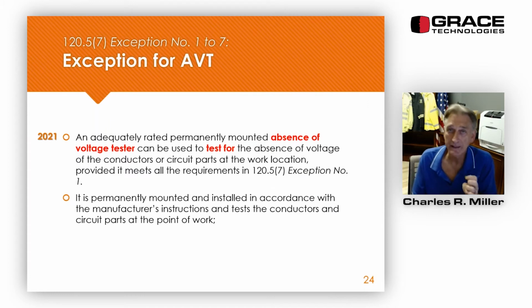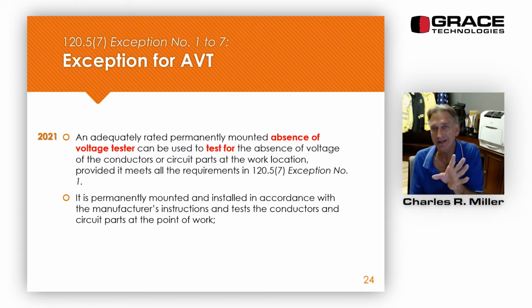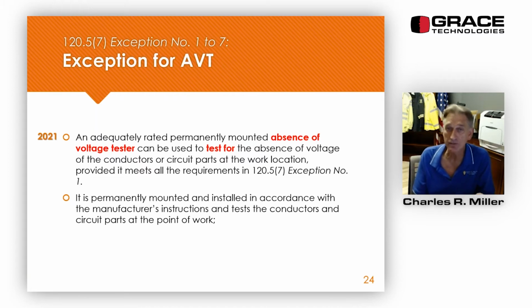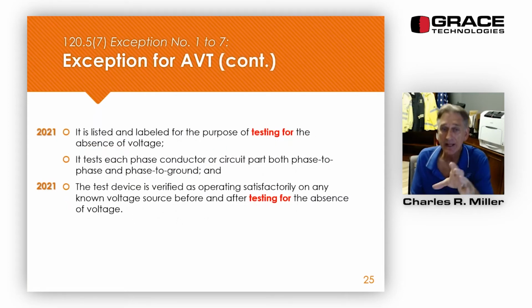All right, there's an exception in the testing for the absence of voltage. And what this exception says, and there was a little change in the 2021 edition, it just changed the wording to an absence of voltage tester, which is exactly what the device is. This device, and there's a couple of them out now, goes on to equipment, but the device has to do everything we have to do, and that's what this slide and this slide tell us.